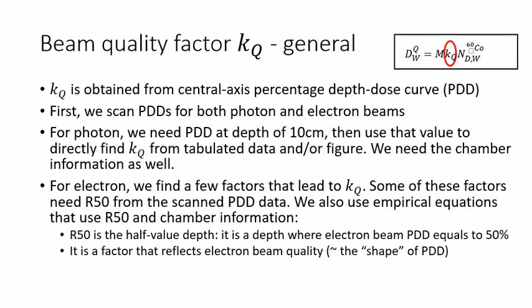If we remember, R50 is the half value depth. It is defined as a depth where electron beam PDD equals to 50%. R50 is a very important factor that reflects the electron beam quality or determines the shape of the electron PDD.